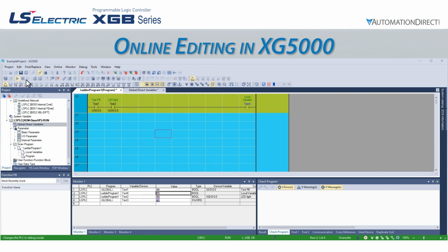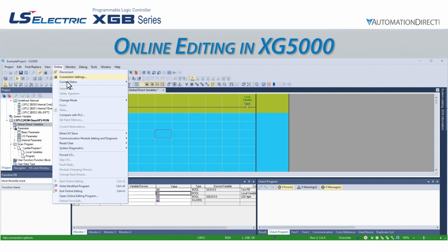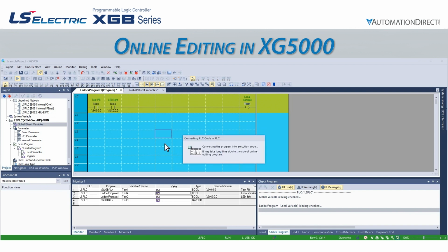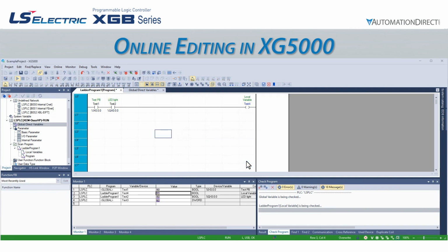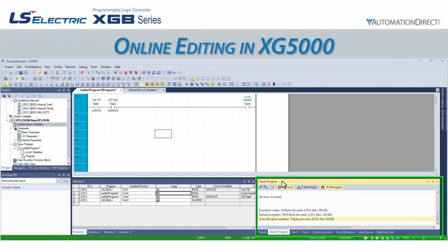If we are happy with our changes and ready to send them, we can click the Write Modified Program button in the upper left corner, or we can go to Online, Write Modified Program. The software then checks the modified project and, if there is no error, transfers the project to the CPU without going into stop mode or interrupting the CPU scan. If there are any errors, the software displays them in the Check Program window in the lower right corner of the software. These errors will need to be addressed prior to the project being written to the CPU.